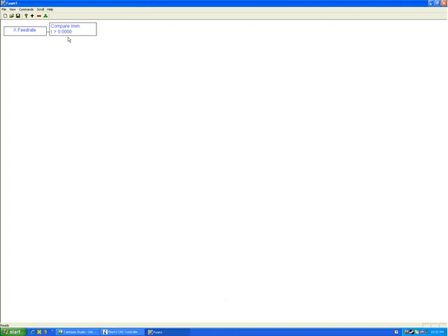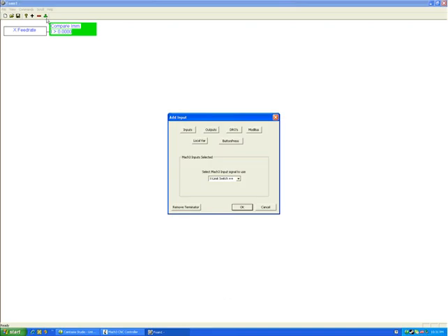So we're asking the question, is the input to this lobe greater than 0? When we click OK, we can now see that the box says it's a compare immediate logic. If the input is greater than 0, it will be true. Well, for this particular example, all we need to know is that it's true. If that's true, then we activate the relay. So we can click on that lobe and say terminate it.